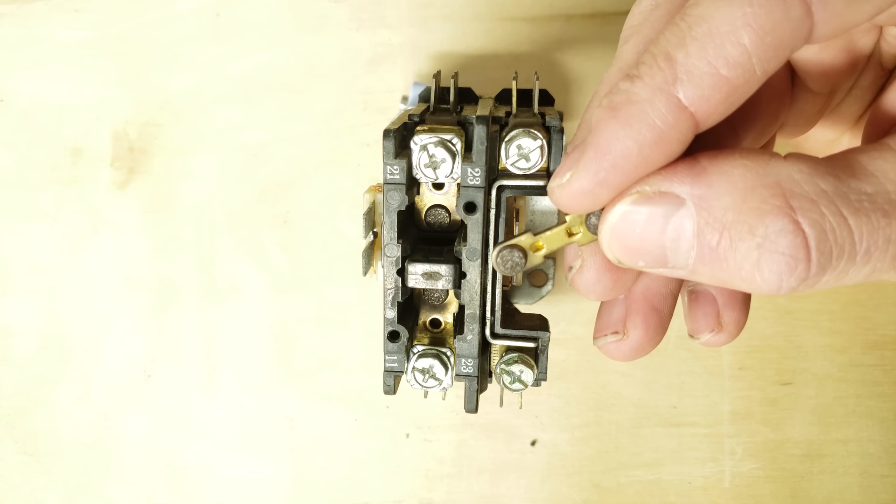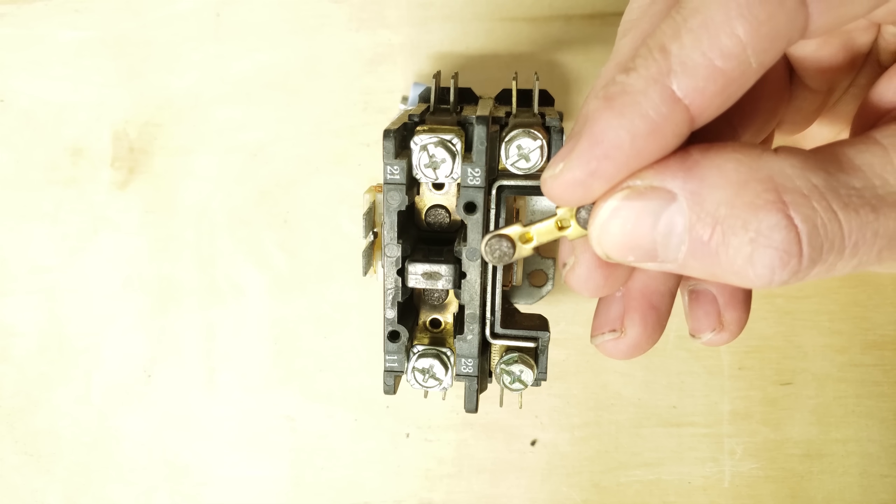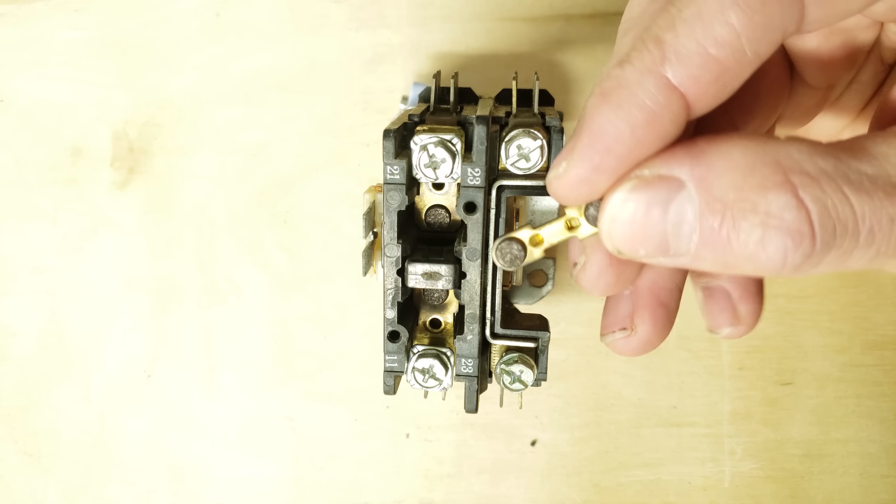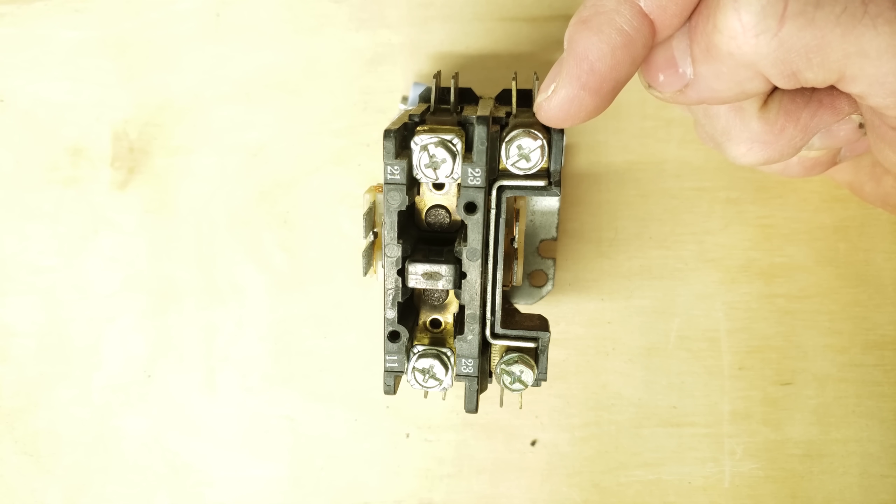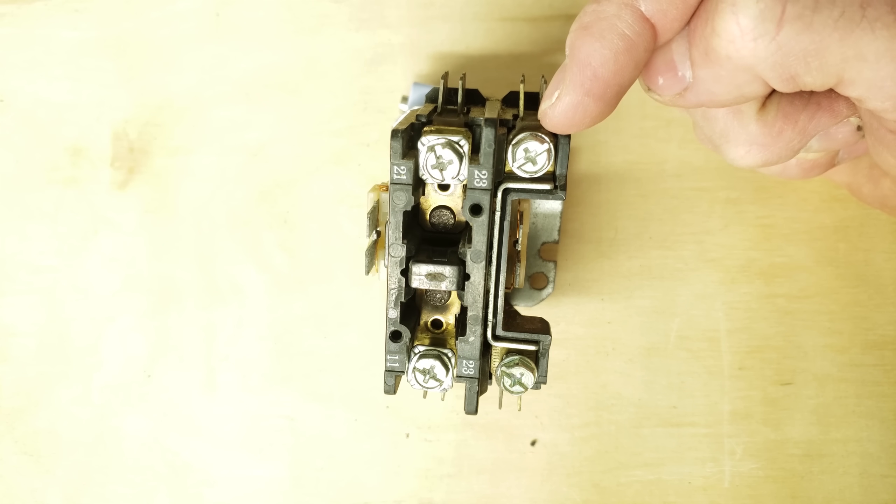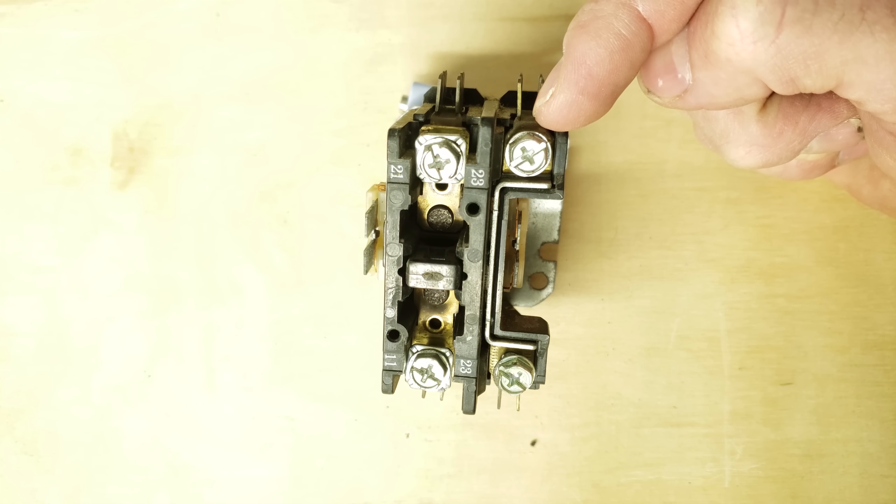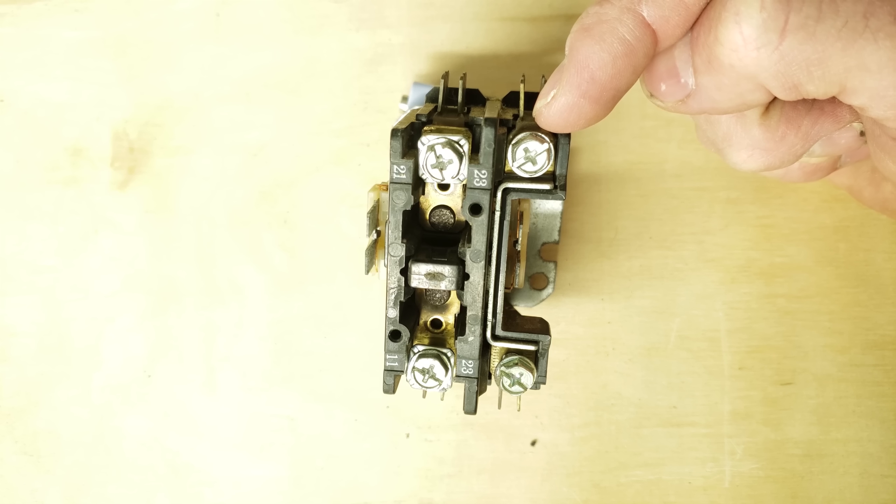I wouldn't recommend trying to file them while this is in place and trying to reuse the contactor. I would suggest that you just replace the contactor. They're not very expensive and this way you know you're not going to have that problem again. The other thing is you want to take an amp draw on the compressor to see if there's a problem and check the refrigerant charge just to make sure that the unit is operating correctly.